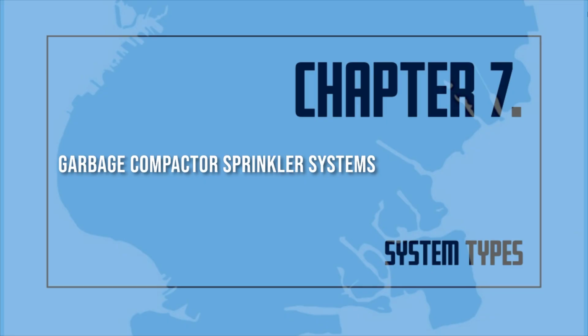The certificate of fitness holder shall conduct an inspection of the entire sprinkler system at least once a month. Special attention should be given to the condition of the sprinkler heads in the compactor chute and the compactor room. Any defects or violations shall be recorded in a detailed inspection report. All inspections are recorded on a card that shall be kept near the main control valve. The certificate of fitness holder shall sign and date the card each time an inspection is made.